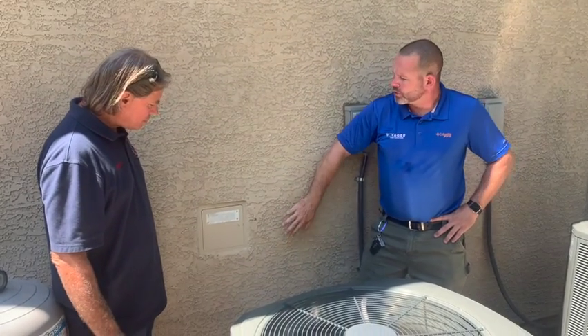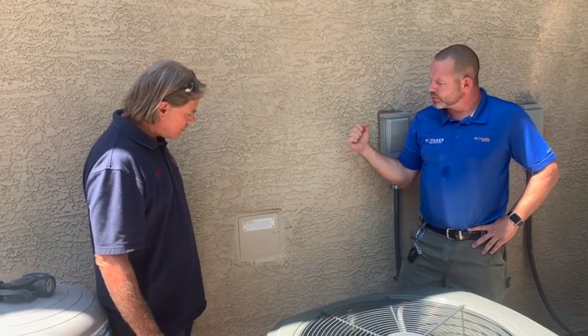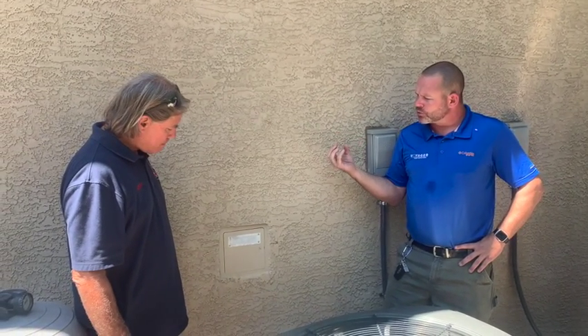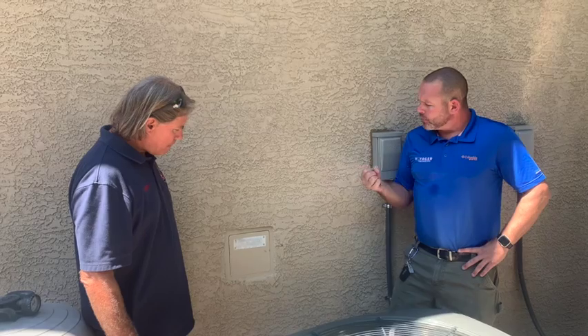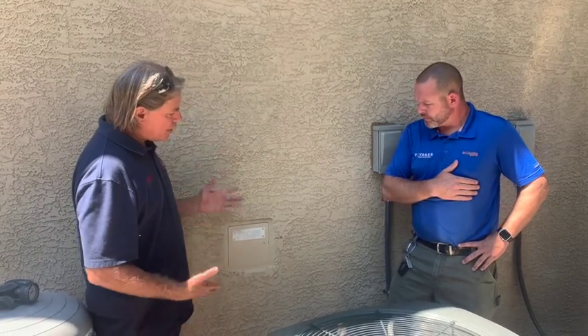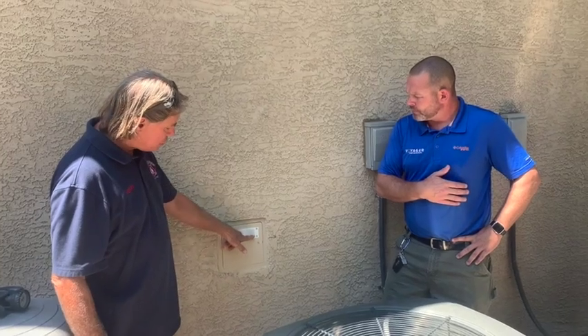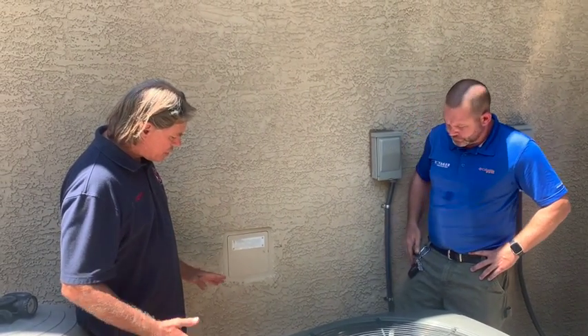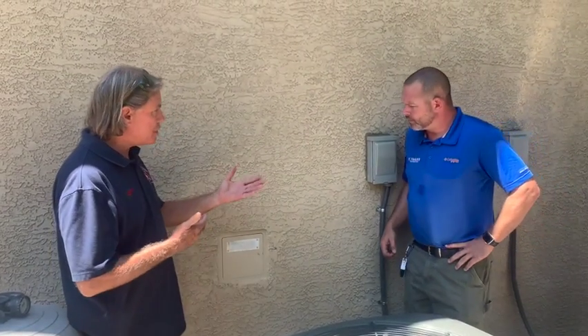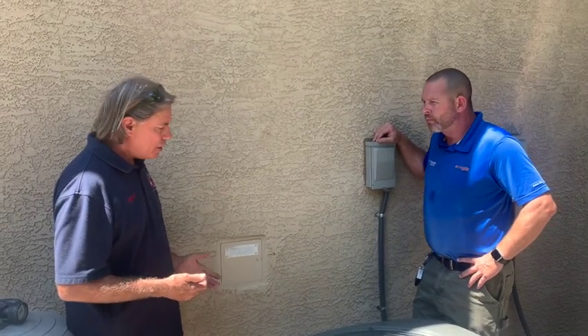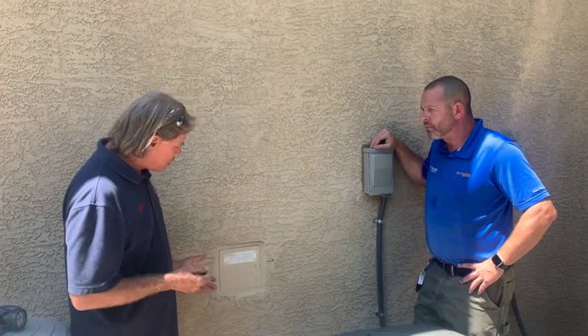Excellent. All right. So as far as homeowner maintenance of the system, we're going to do a visual check in the garage, look on the outside for that drain to see if that drain is leaking, and what else can we do? Well, when you come around here to this side of the house, it's usually the most demanding area where the fire sprinkler system has been piped down to a valve that we call the inspector's test. The inspector's test has a couple of different functions. One, as you said, is for maintenance for the homeowner or for a technician.